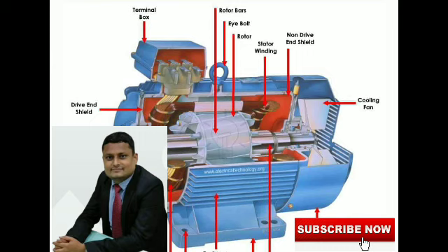Once again, what will be the shape and size of the stator conductors? AS less than 5 mm square for circular conductors. AS greater than 5 mm square for rectangular conductors. For rectangular conductors, the width to thickness ratio must be between 2.5 and 3.5. Standard bare sizes of round and rectangular conductors from standard tables.